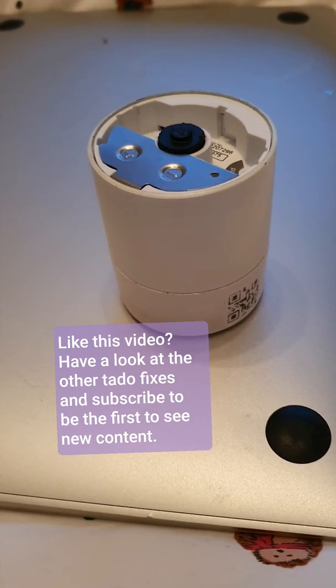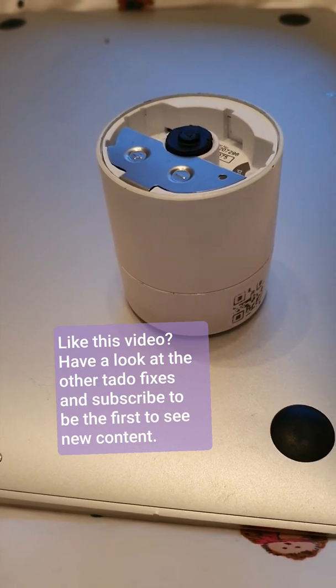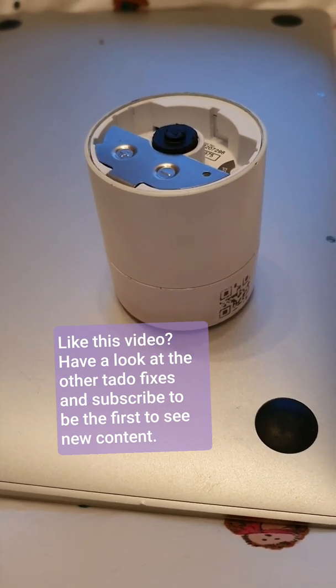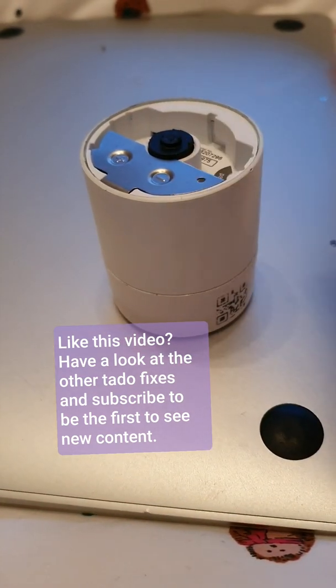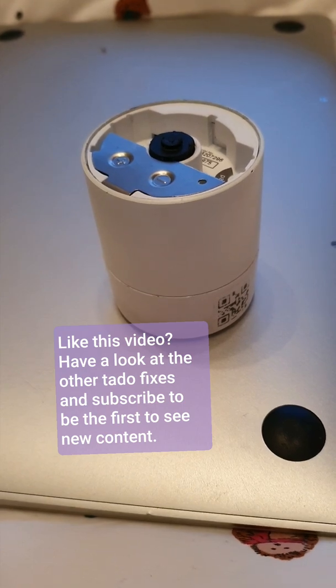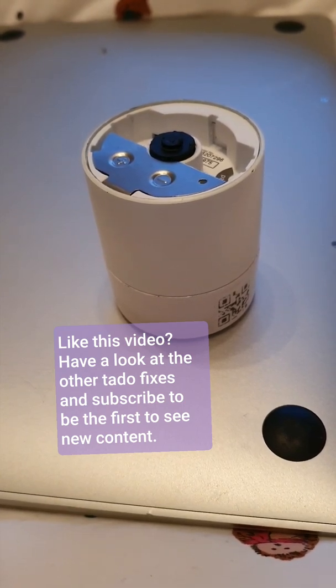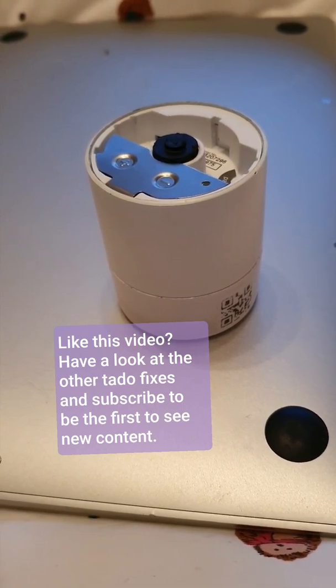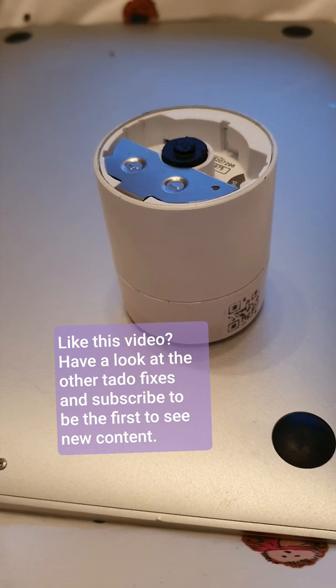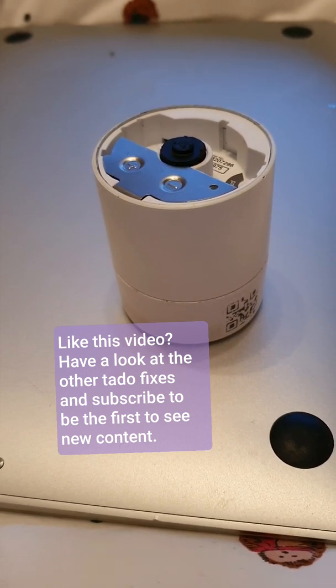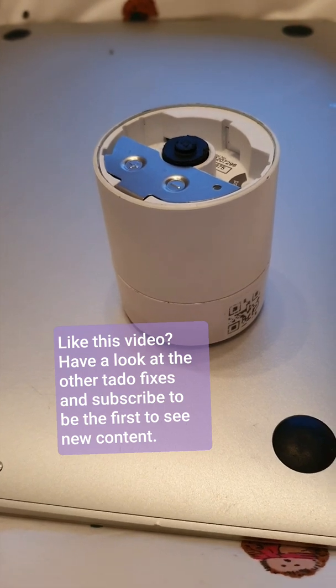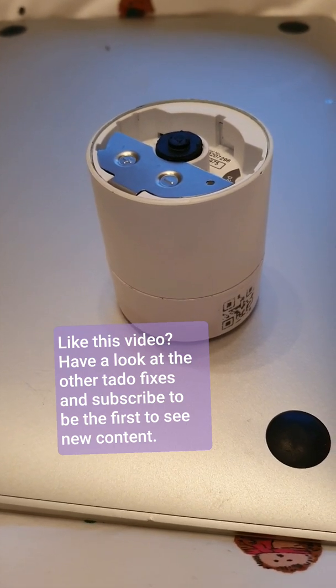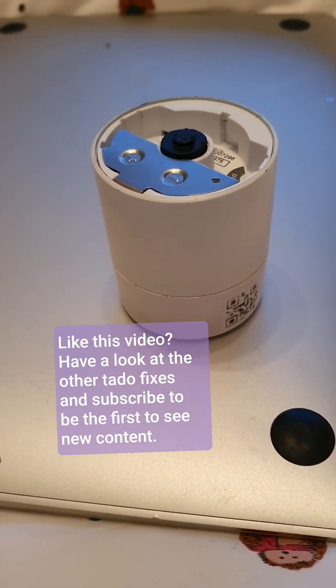So easy solution. If you're having a problem with your TADOs, take out all of these and just replace one at a time and see if the system fires accurately. If it's not firing accurately, also check your water levels to make sure that the water levels in the boiler are above the minimum, but not at the maximum. Check that as well.